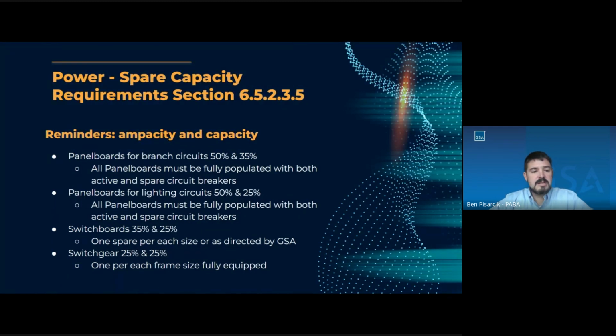of similar breaker sizes. And that's why it is directed by GSA, because there could be situations where putting certain size breakers in does not make sense, and we're certainly open to that. You can discuss that with the designer. For switchgear, it's 25 and 25 for both, and one per each frame size, fully equipped. Again, a lot of times this gets mistranslated. There's such a thing as a prepared space, which is not a spare circuit breaker. I've had people try to sell that as a spare circuit breaker, and it certainly isn't. We want to have frame size breakers that we can use to replace breakers that are currently in that gear. So that's important to have.